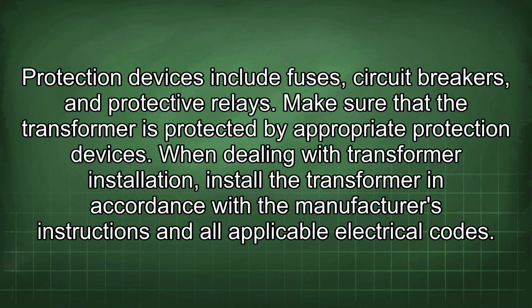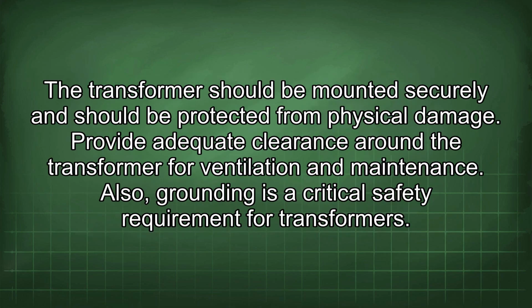When dealing with transformer installation, install the transformer in accordance with the manufacturer's instructions and all applicable electrical codes. The transformer should be mounted securely and should be protected from physical damage. Provide adequate clearance around the transformer for ventilation and maintenance.